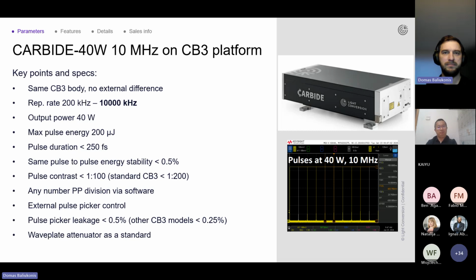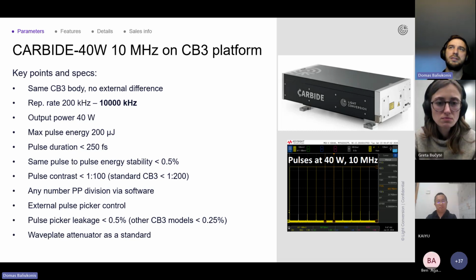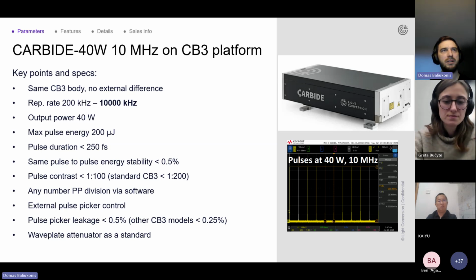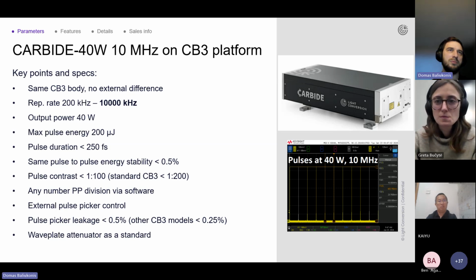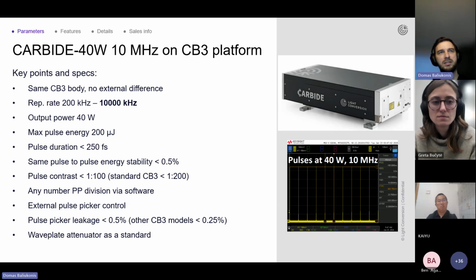To introduce the main parameters of the laser: as I mentioned before, it's up to 40 watt of output power. The repetition rate can be selected from 200 kilohertz up to 10 megahertz. At 200 kilohertz we would have about 200 microjoules pulse energy, and the pulse duration is, as our standard, below 250 femtoseconds. Even with this 10 megahertz frequency, we remain at the same pulse energy stability, which is below 0.5%.